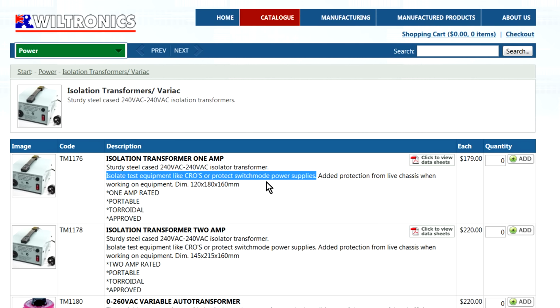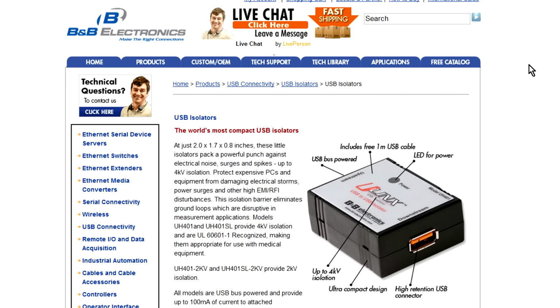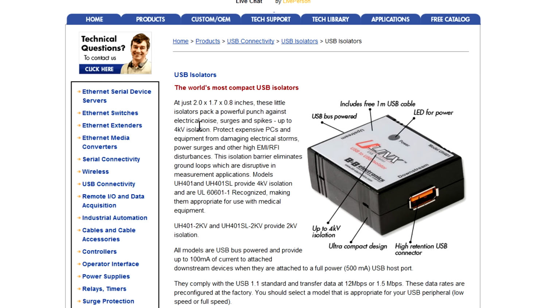Your oscilloscope should remain, for safety reasons, a mains earth grounded product. So you should use the isolation transformer to power your particular product under test, and this can be an essential bit of kit in any test or repair lab. And if you've got a USB product and you want to isolate that, you don't want your USB cable to cause any issues, then you can get one of these, rather an obscure product, a USB isolator. There's not too many of them around, but basically it's got a transformer in there with some high speed to couple not only the power lines but the data lines as well at full USB speed.